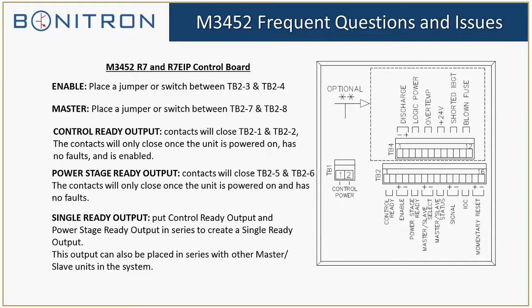Likewise, this can be set for either master or slave. In most cases people are using this as a standalone unit, so it needs to be set for master. The easiest way to do that is to just place a jumper here. If there's no jumper or switch here, then the unit will always be a slave, following the master.